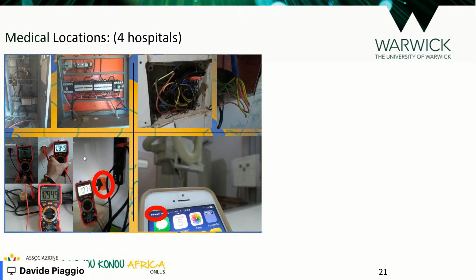This basically hinders the first safety net of the hospital room, or office room, whatever room, because if the voltage is too high, this system won't work. The way this system works is that if there is a problem with the insulation in the device and we are exposed to a voltage, the current, rather than flowing through us, will flow through the least resistant path to the ground, which should be this pin. But this is not the case, because we have this voltage here.